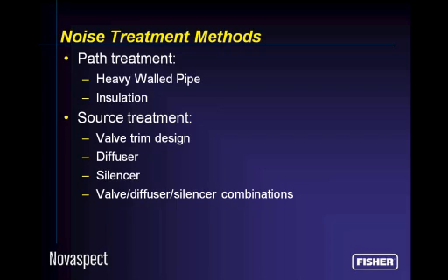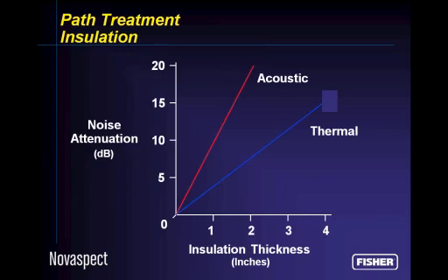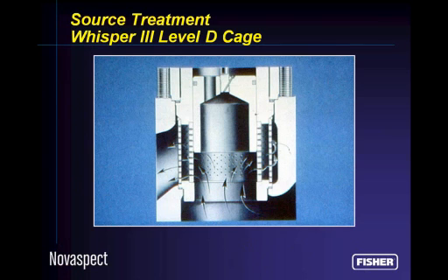We're going to use source treatment to reduce the noise level by creating something different in the valve to not let the valve even start to make noise. And we can do this by the proper selection of the trim, by using a diffuser, a silencer. We've got different ways to do that. You can see here that thermal insulation, for example, is worth 10 dBA of noise attenuation if you give us 3 inches thick of insulation, calcium silicate, for example.